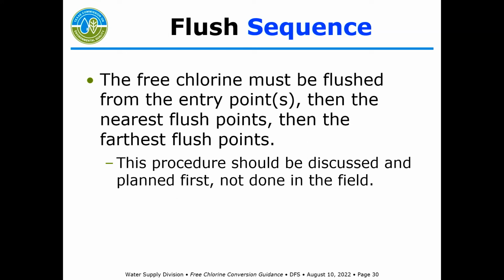All right, let's come back to sequence. The free chlorine must be flushed from the entry points to the nearest flush points, and then move on through the system. You don't want to go and flush at the end of the system right off the bat during your free chlorine conversion.